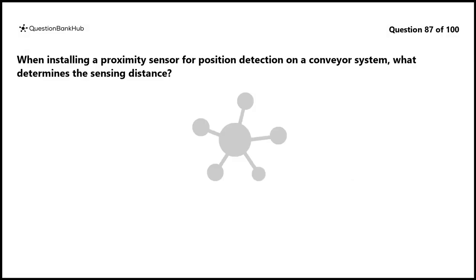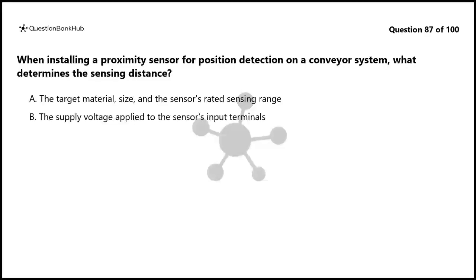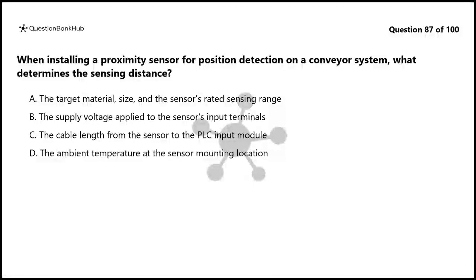Question 87. When installing a proximity sensor for position detection on a conveyor system, what determines the sensing distance? A. The target material, size, and the sensor's rated sensing range. B. The supply voltage applied to the sensor's input terminals. C. The cable length from the sensor to the PLC input module. D. The ambient temperature at the sensor mounting location.